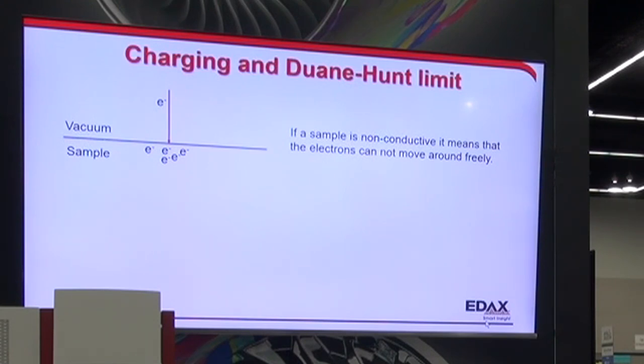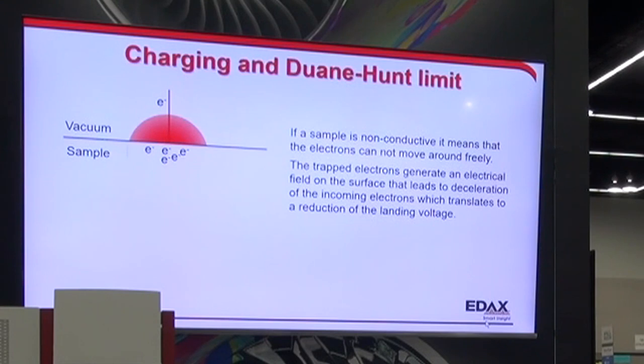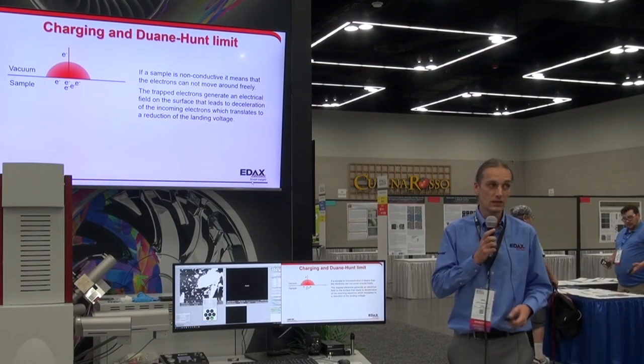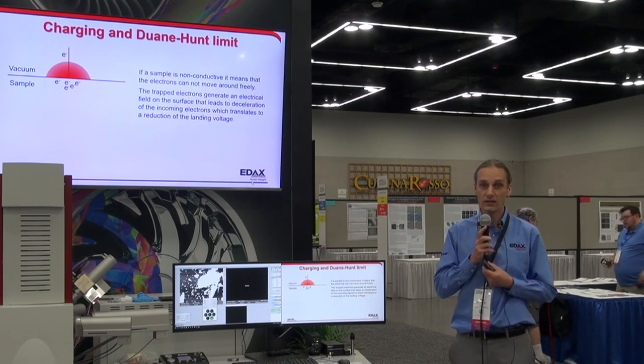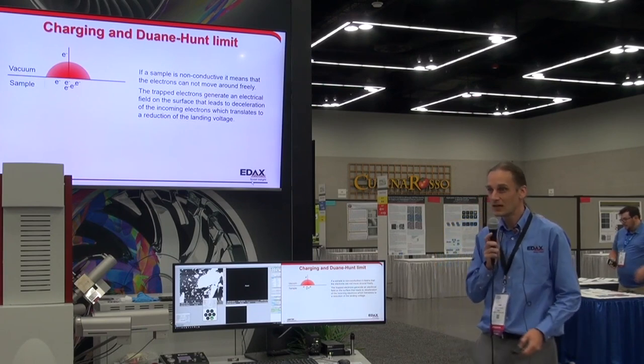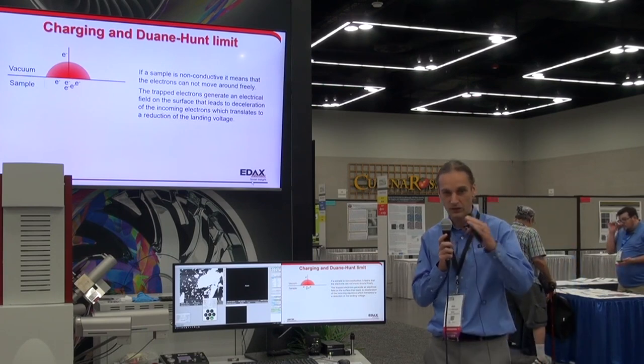If we have a charged particle sitting on the sample, we will have an electrical field. With a negatively charged buildup, we generate a negative field, and we're trying to push a negatively charged electron down through that field. So you'll have Coulomb interaction, essentially slowing down the incoming electron. The landing voltage of that electron is not the acceleration voltage we put through the gun.